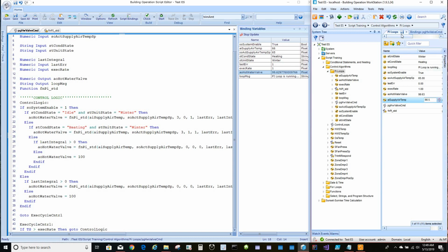Increase, then it goes up, it hits 100, and now it pauses. And it pauses so that we do not wind up our integral to a value so far out of reach that once we need to reset, it would take hours possibly for the integral to subtract the partial sum of the error down low enough to get it back in the range that it's needed to affect the output signal.